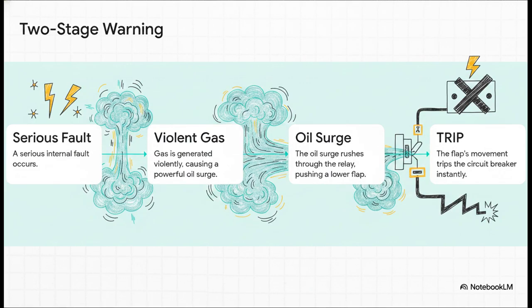But what happens when things go from bad to really bad? And fast? That's stage 2, the trip. If a major short circuit happens inside, gas is created so violently that it causes a powerful surge of oil to rush out of the main tank. This wave of oil slams into a lower flap inside the relay, pushing it forward. That movement closes a totally separate switch, and this one is wired to immediately trip the main circuit breaker. No alarm, no warning, just disconnect, now. It's all about preventing a catastrophic explosion.